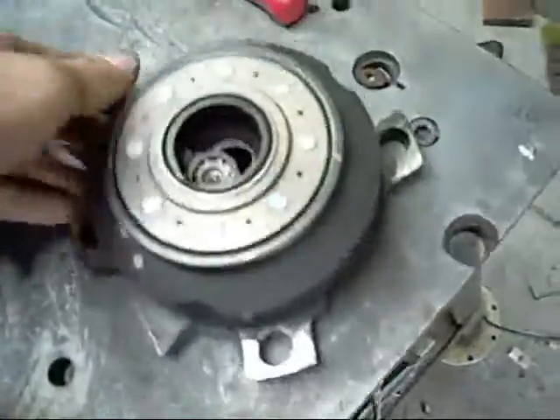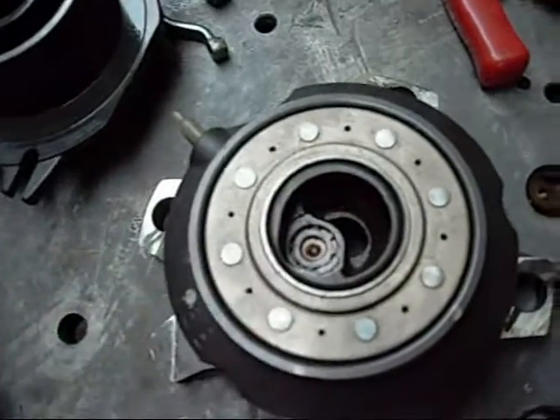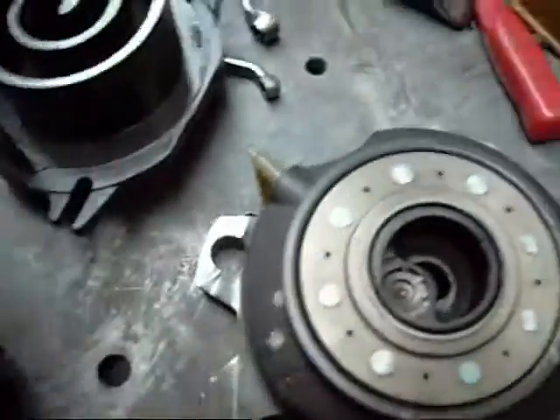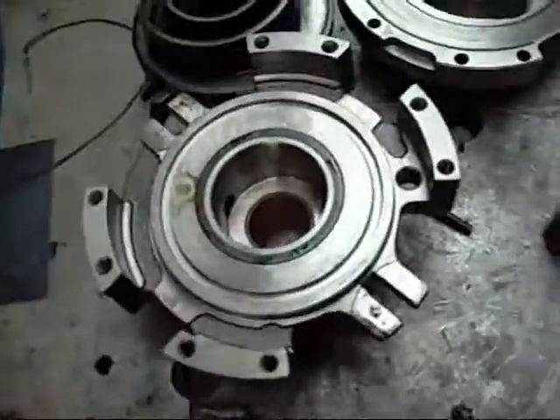There's a little oil drain off tube here. You can see that little over-pressure relief valve in here — I'm guessing if the high pressure side becomes too high, it will blow off and discharge pressure out to the low pressure side. Likewise with this one here.